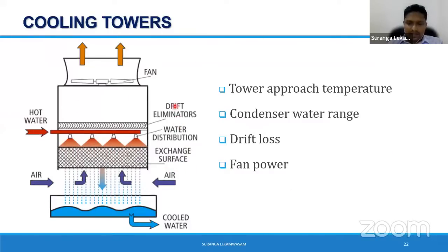For you to specify the cooling tower, there are certain parameters to be looked at. Importantly, you have to specify the condenser water range. That means the temperature range your cooling tower works at. In our designs, we were using 37 hot water inlet and 32 cooling tower exit. That is called range. Nowadays, we rely on 35 and 30 because of the efficiency improvements. So you have to specify that one.